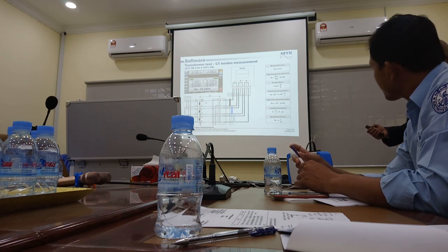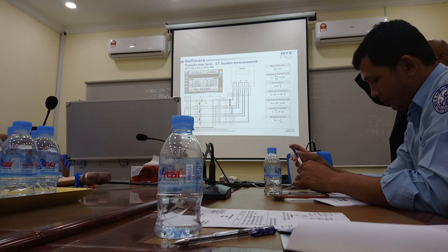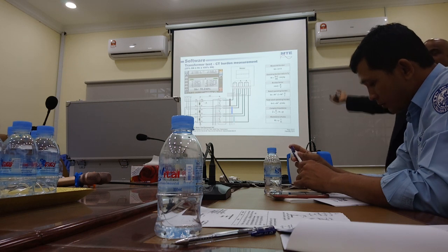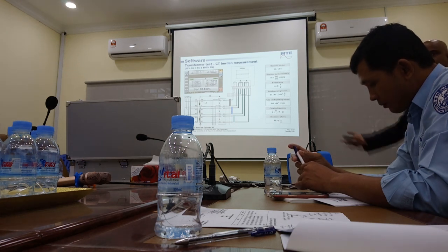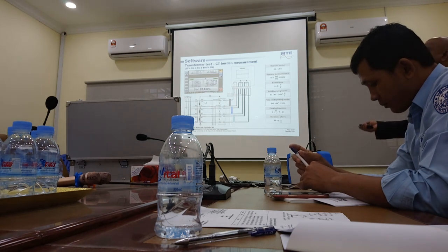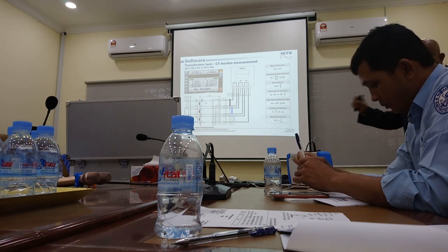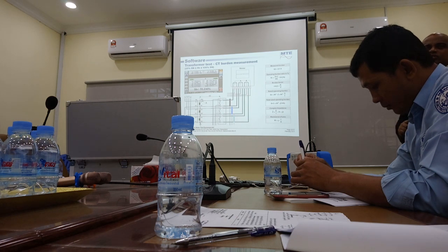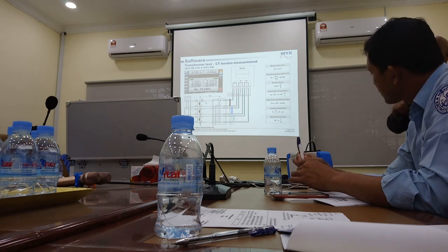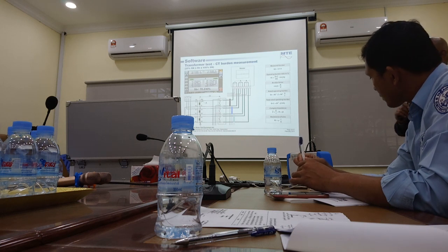Very, very small. Maybe he just put one lamp or something, or when the customer is not at home or customer plant is shut down, yeah, then it's very difficult. You need some current, right? You need some current because the resistance is so low already, maybe in a few ohms, it is all millivolt or microvolt. So you need some decent current through the wire.